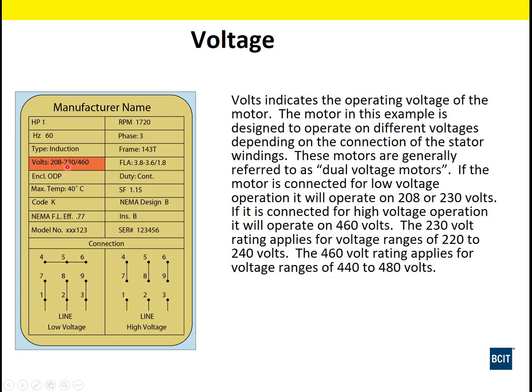What that means is, if we go over here to the current rating, the FLA, full load amps, we have a little bit of a broader current range here. So the windings, the conductors, are sized enough to hold that slightly higher current. So we can put 208 volts there all the way up to 230 volts. Now the insulation is sized to handle that voltage. Conductor size for current and insulation rating for voltage.